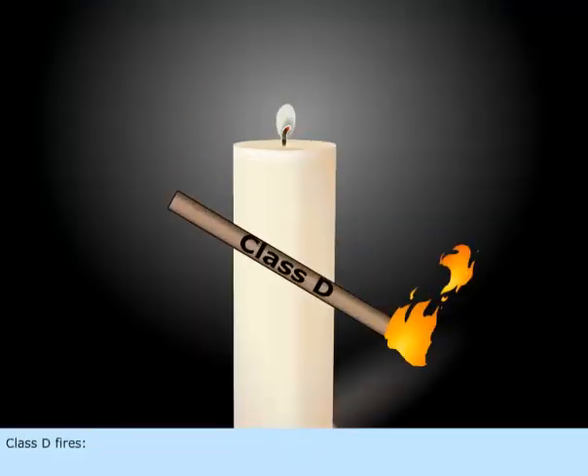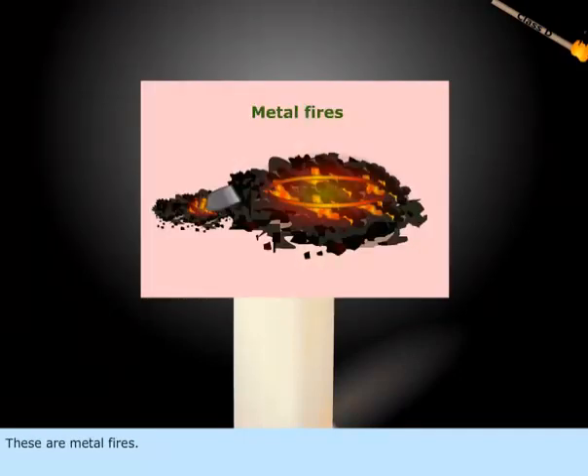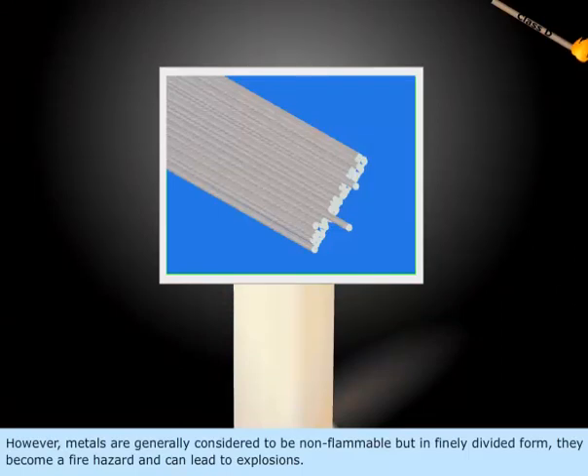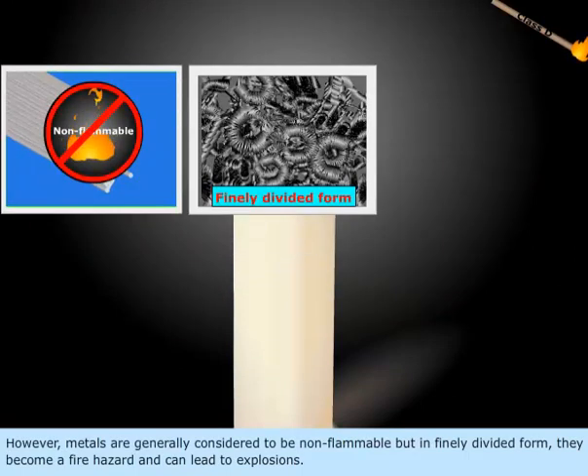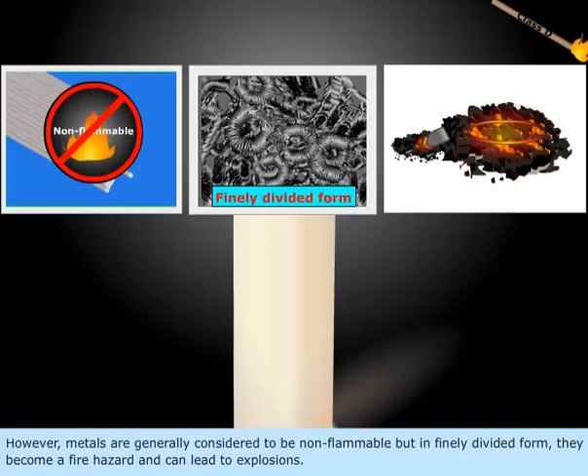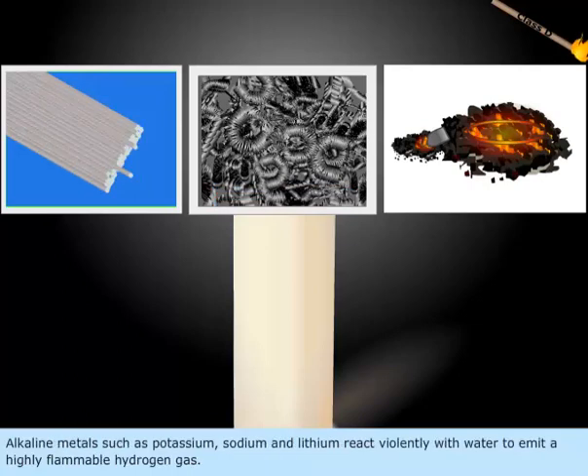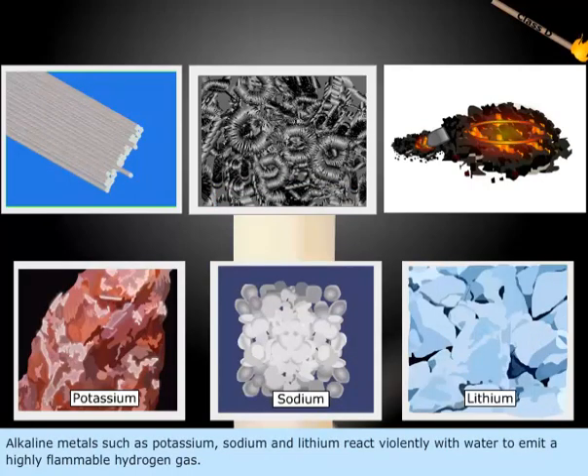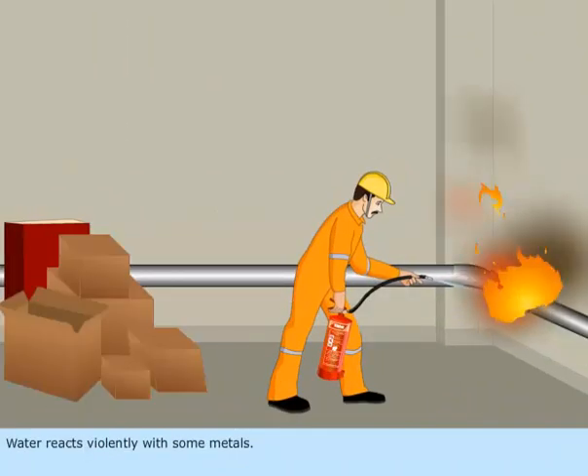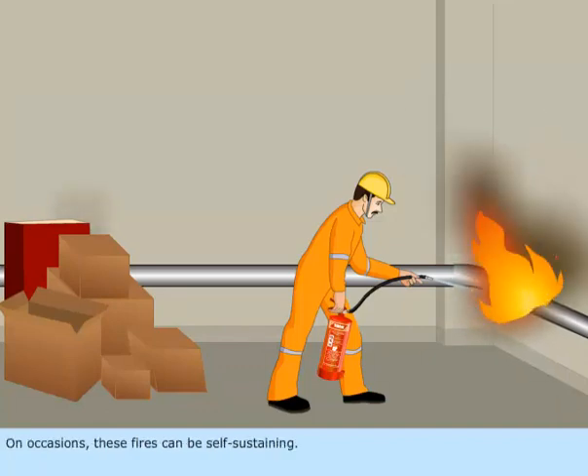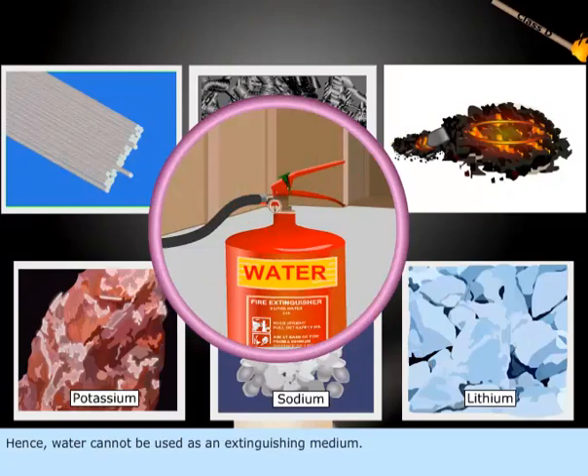Class D fires. These are metal fires. However, metals are generally considered to be non-flammable, but in finely divided form they become a fire hazard and can lead to explosions. Alkaline metals such as potassium, sodium, and lithium react violently with water to emit highly flammable hydrogen gas. Water reacts violently with some metals, and on occasions these fires can be self-sustaining. Hence, water cannot be used as an extinguishing medium.